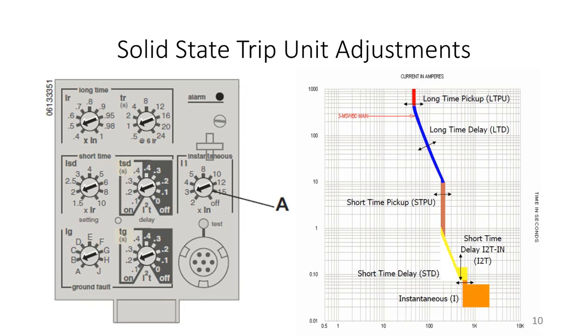And then you will see feeder breakers or branch breakers. But instead of putting that large 1200 or 1600 or 2000 amp circuit breaker as the main coming off of the load side of the transformer, you may think, okay, why don't I come out with three smaller circuit breakers instead? The three smaller breakers may give me a better solution because I am dividing the load in a different way. So sometimes this solid state trip unit is amazing technology. I'm not mocking it, but it's not always the answer.